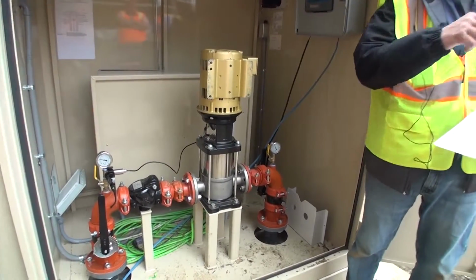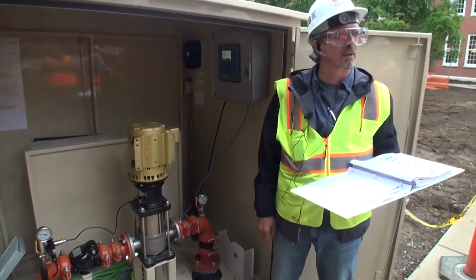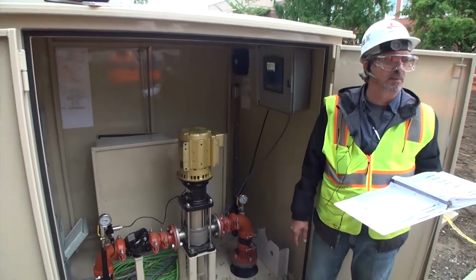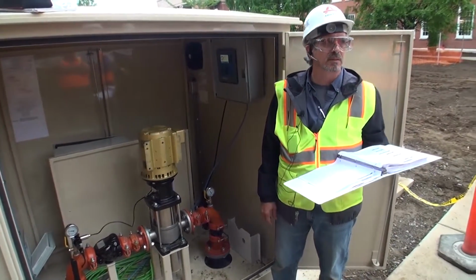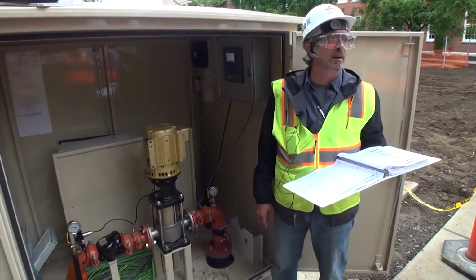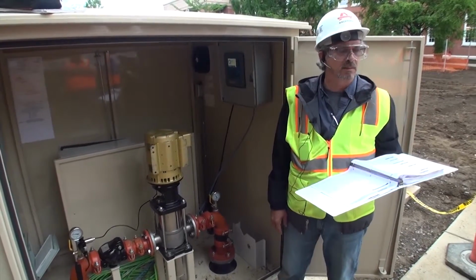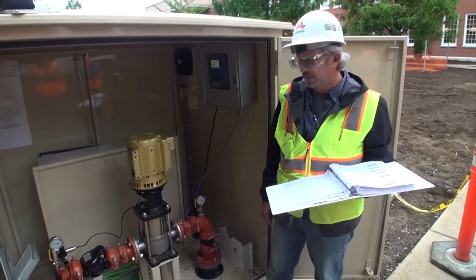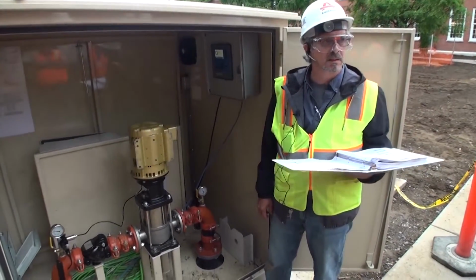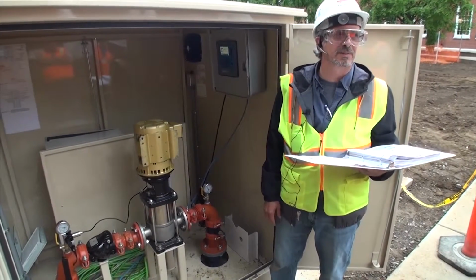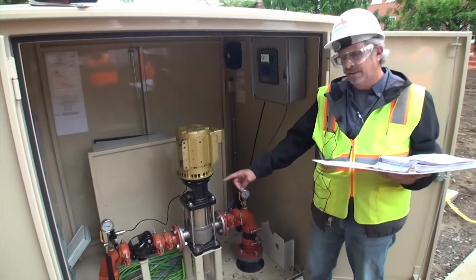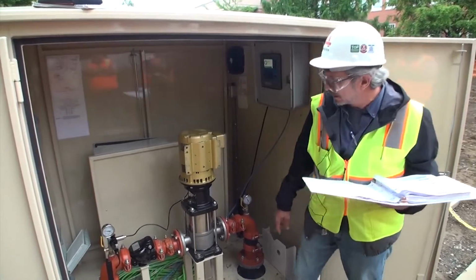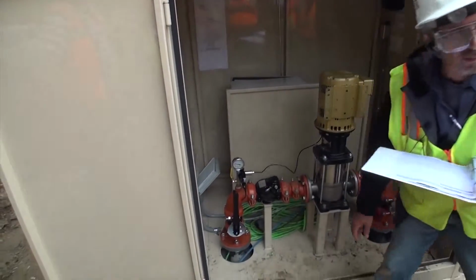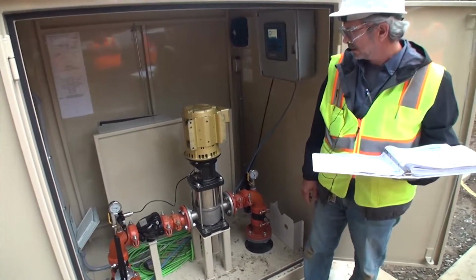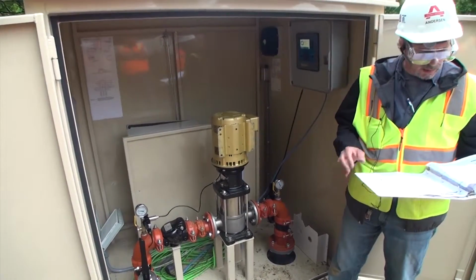Yeah, good question. The transducer should be okay with the pressures you're going to run. You're not going to run that much air pressure. It'd be dangerous. A couple hundred pounds is fine. 150? Sure. Yeah, easily. Probably 350? No, not good. You don't want to do that. So I said the transducer will be fine. You don't want to damage the gauges by putting that much pressure on them either. This one here goes up to 200, so you'll be okay with that.